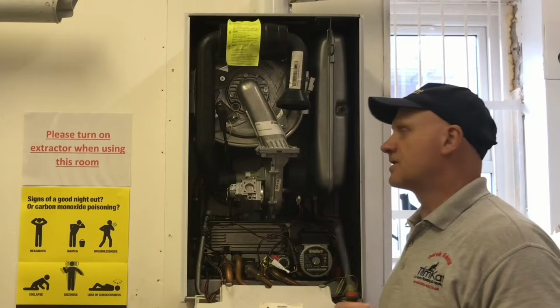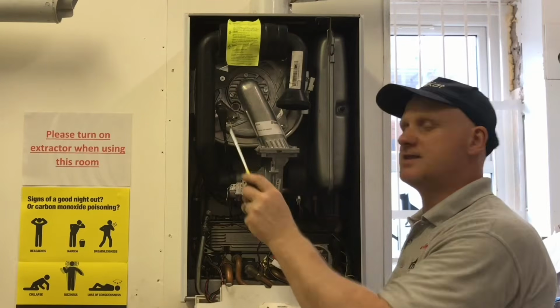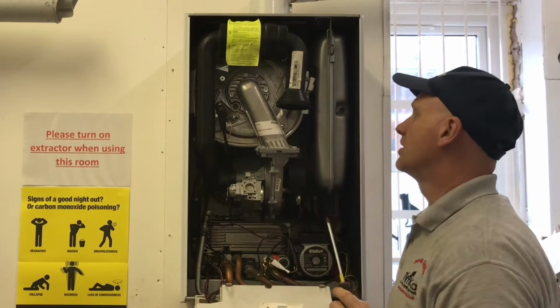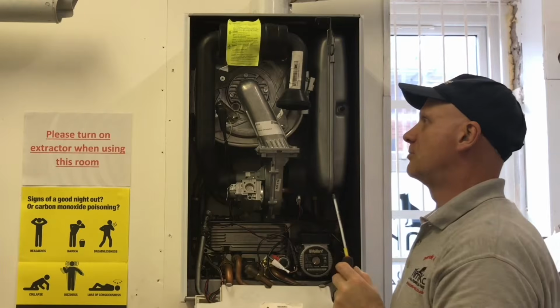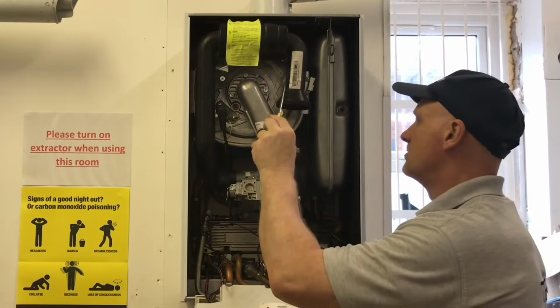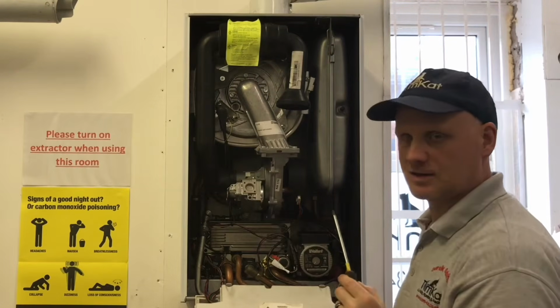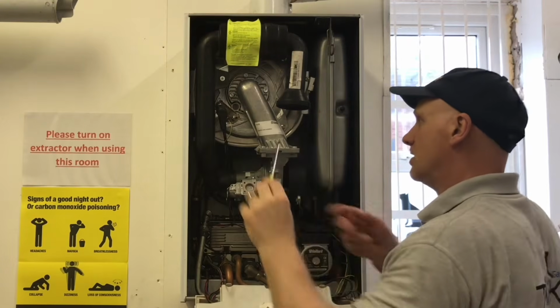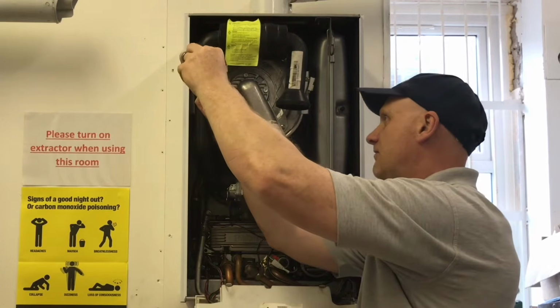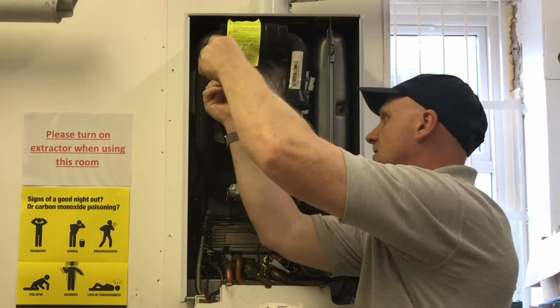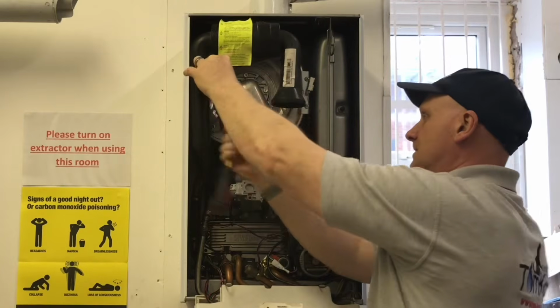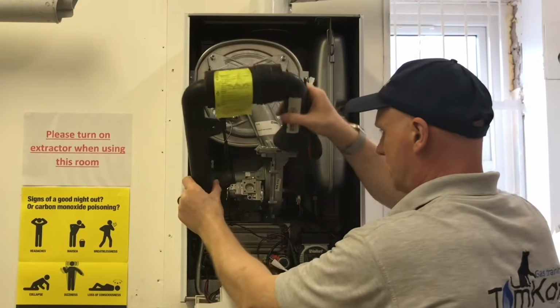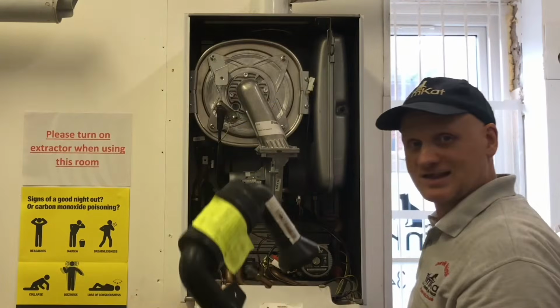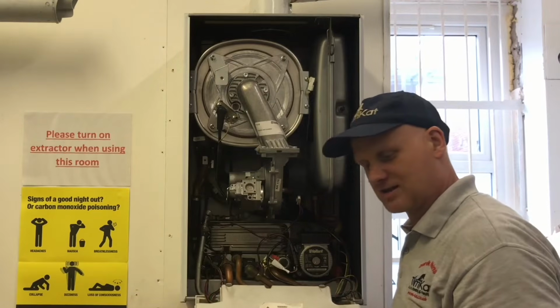So first thing I've got to remove is this air inlet. So again, like I said, this is where the products of combustion come in. So I need to remove this first to get at the nuts for the burner. So it's just basically a Phillips screw. Drop it down and it comes off. As simple as that. So that's the first thing to get off.